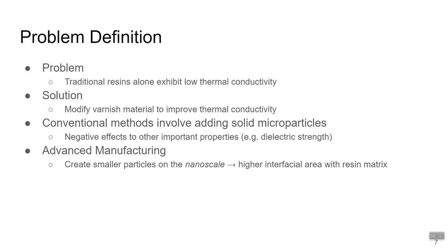The problem is that traditional resins alone exhibit low thermal conductivity. One solution is to modify the varnish material and improve the thermal conductivity artificially. Conventional methods exist and they use solid microparticles mixed into the resin. However, this can have negative effects to other important properties, such as the dielectric strength.